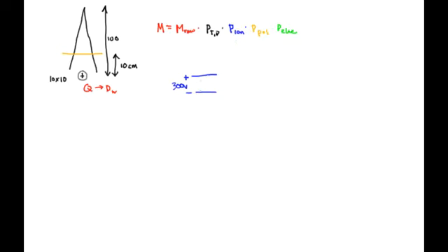All right, so now let's look at these last two factors, P polarity and P electrometer. First, polarity. You'll see the chamber has the positive electrode here and the negative electrode here, but you could flip those and put the negative one here, positive one there, and you would get a different collection efficiency because the chamber is not symmetric with respect to the collection efficiency on those two electrodes. So that's how you actually do it. When you work through the protocol, you flip the voltage and you measure the collection efficiency difference, and that gives you a polarity correction factor.